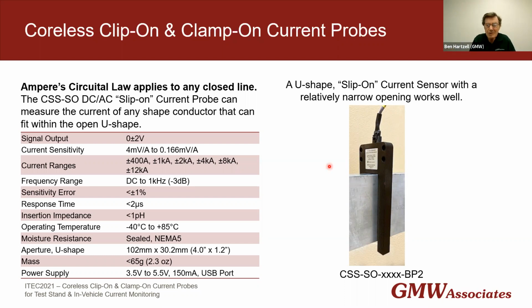And power consumption is low, so it can actually be used with a battery that's mounted on the outside of this. Current ranges 400 amp to 8 kiloamps, 12 kiloamps. DC to a kilohertz, sensitivity error 1%, response time 2 microseconds. Again, a very low insertion impedance. Operating temperature -40 to 85 degrees C. It's sealed again. The aperture is 102 by 30 millimeters, so that's about 4 by 1.2 inches. Mass 65 grams, or about 2 ounces. 3.5 to 5.5 volts, 150 milliamps. So again, this can be used with a USB port.